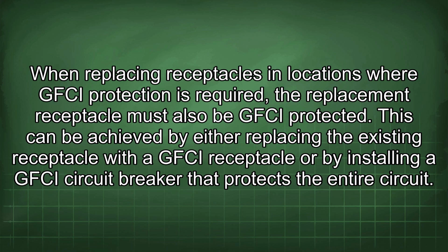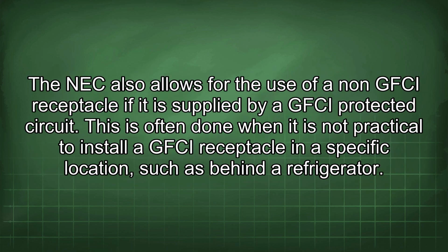When replacing receptacles in locations where GFCI protection is required, the replacement receptacle must also be GFCI protected. This can be achieved by either replacing the existing receptacle with a GFCI receptacle or by installing a GFCI circuit breaker that protects the entire circuit.